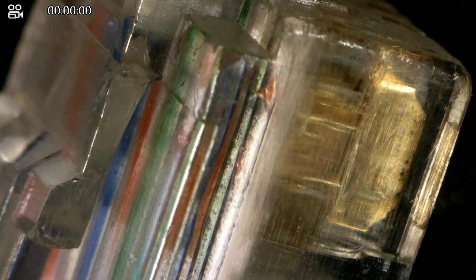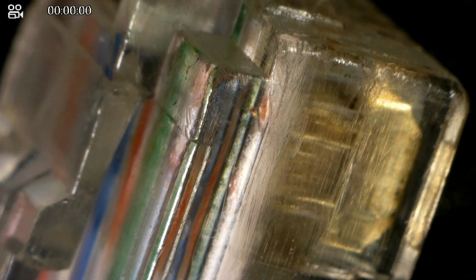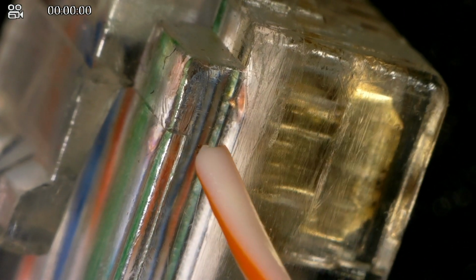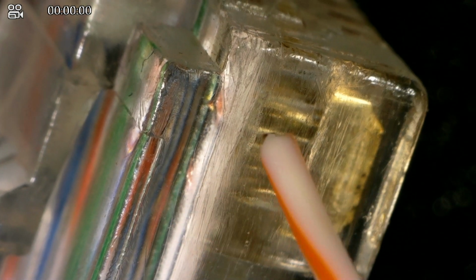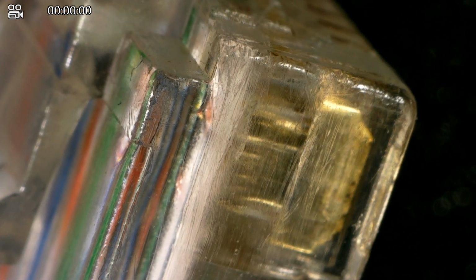The connector came down on the cable, and let's see if we have one that shows. I'm not sure if you can see it or not here. Let me see if it's better with the other one. This one is damaged. All right, you can see it a little bit better here. Let me just focus it a little bit for you. You see, this connector came down on the cable, and you can see tiny signs of pinching here. It actually came through the cable. That means there's a good connection going on.